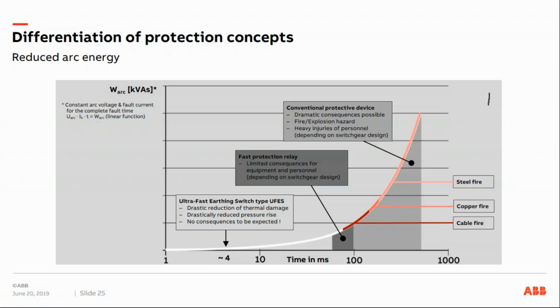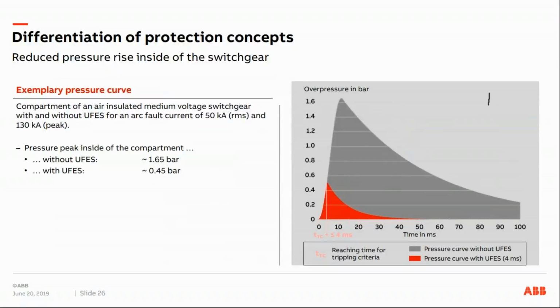However, that one compared to the UFES is still leading to an energy development that is way too slow compared to the ultra fast earthing switch type, where you don't expect any consequences on your equipment, and the energy and the thermal damage level will be decreased drastically, and there won't be that high of a pressure rise. Here I wanted to show you again the overpressure development for an arc fault current occurring for a 50 kA RMS and 130 kA peak for a switch in a switchgear with and without the UFES. Without the UFES, you can see that there is an overpressure of up to 1.65 bar, whereas with the UFES, there's even less than half a bar pressure development.